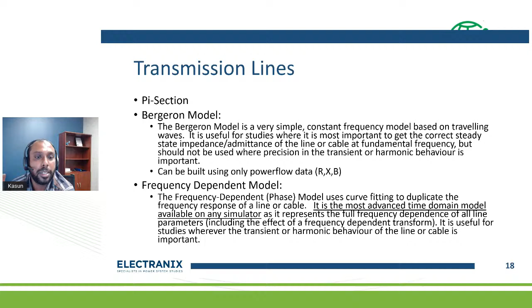The next one is the frequency dependent model. This is the most detailed model in PSCAD. It can model right-of-way data, transmission line conductor characteristics like DC resistance, sag, the dimensions between conductors, transmission tower resistances, and many more details. When you put it all together, it calculates the RXB — the resistances, inductances, and capacitances — for each and every frequency, through the frequency dependent model. This is one of the most advanced models. If you do lightning studies, or studies where the high frequency part is important, this is the model to use. So that's one of the main models in PSCAD EMTDC.